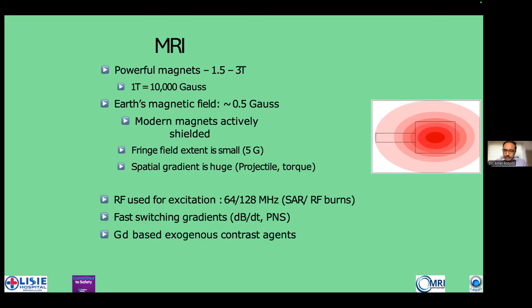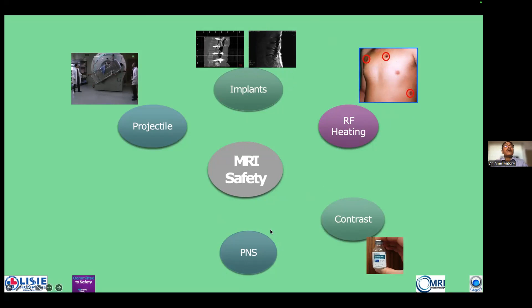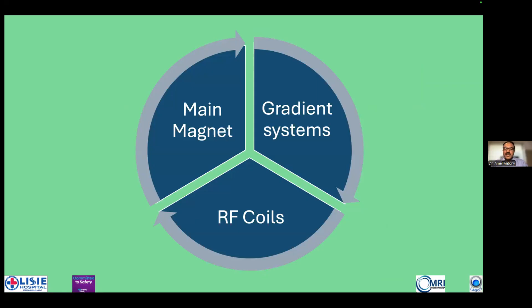Now, the key to all this MR safety is, of course, projectiles. That means free ferromagnetic objects which can act as projectiles, causing damage to the equipment and to the patient who is present. And various implants, whether they are MR conditional, that means they can be used under certain conditions, like maybe in a 1.5 Tesla MRI, or they are completely unsafe, because these implants can either malfunction or get dislodged. And RF heating usually happens from the RF coils, and contrast reaction, not an important concept, but gadolinium-based contrast can cause nephrogenic systemic fibrosis, especially in patients in renal failure. And finally, the varying gradient fields, which can cause peripheral nerve stimulation. So as I said, these are the three components: the main magnet, the gradient systems, and the RF coils.